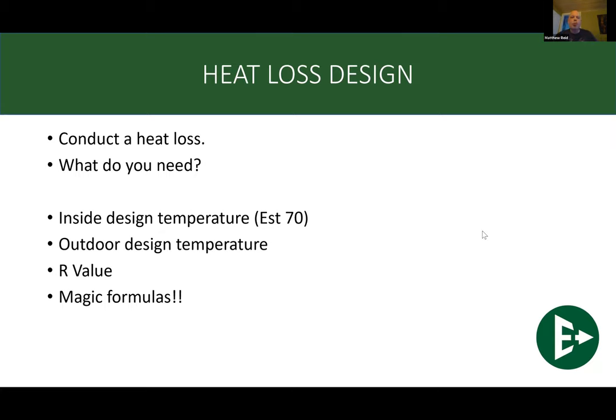So we're going to tell you about conducting a heat loss. What do you need? You need your inside design temperature, which is usually approximately 70 degrees. We're going to be talking Fahrenheit throughout this presentation. Then we're going to be talking about the outdoor design value, your R value, and your magic formula. Now the outdoor design temperature varies from city to city across the country. Here in Barrie, Ontario, I believe we design to minus 10 Fahrenheit, minus 10 or minus 7, something like that. But like you say, it'll vary across the country.